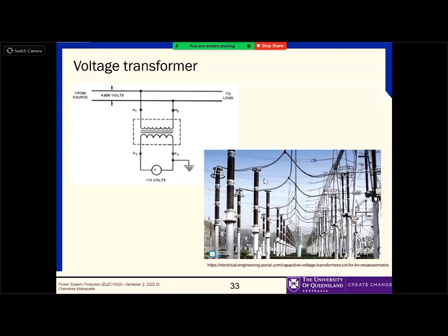So now what it does is feed the voltage to a small transformer here, and then the transformer's secondary voltage is measured. That measurement goes through these columns to the substation control room - it's not measured here, it goes to the substation control room, and there a voltage proportional to this voltage appears on the secondary side. So that is very simple, that's how you do the measurements.